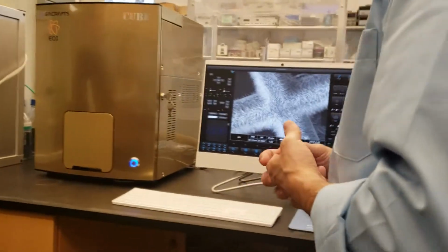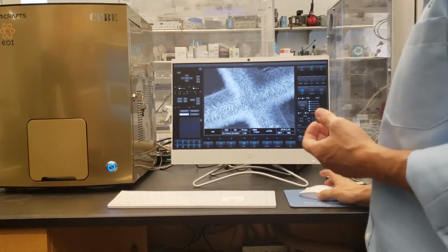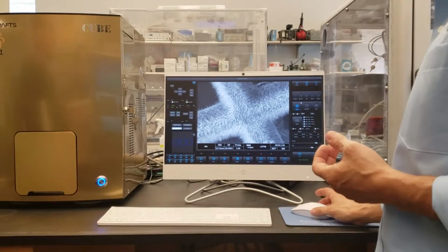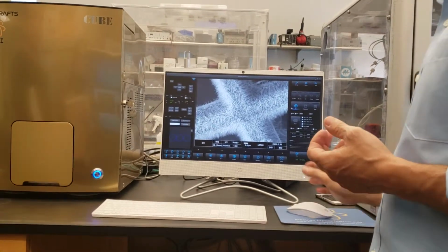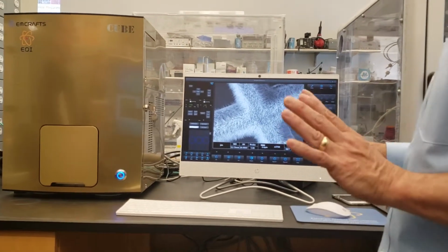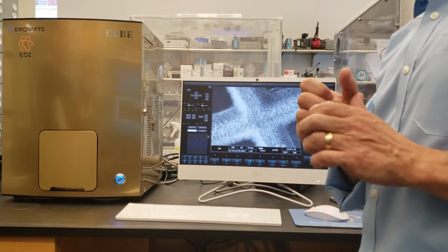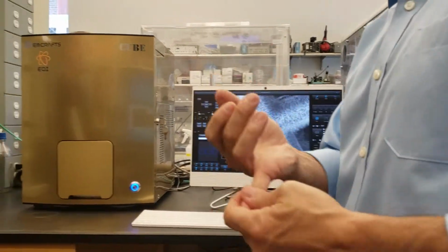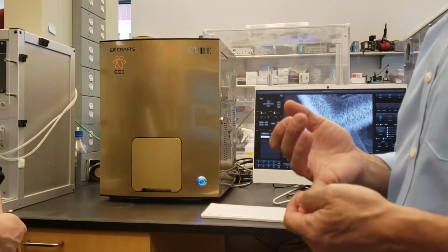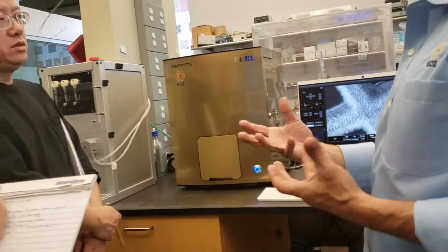We can actually see it building vacuum here, 3 times 10 to the minus 4, and it's getting better, 2 times 10. As soon as it hits around 1, you'll see it goes green. As soon as that light goes green, it allows me to turn run on. Run means we could operate the tool, but I don't do that until this reaches its maximum vacuum, so I wait. And I recommend you guys wait. If we don't wait, then we run a chance of blowing the filament early, losing filament life, right? Because you have a tungsten filament in there, and the life of the filament usually is anywhere from...